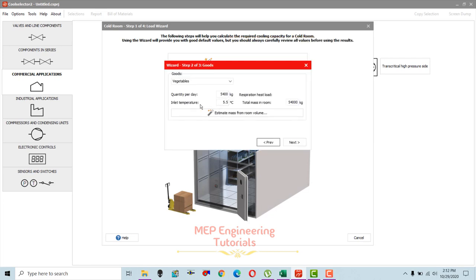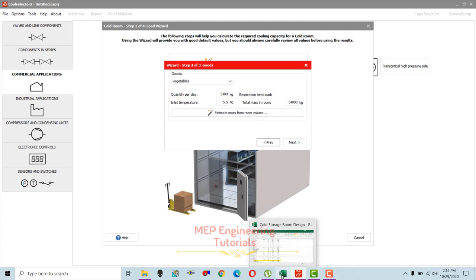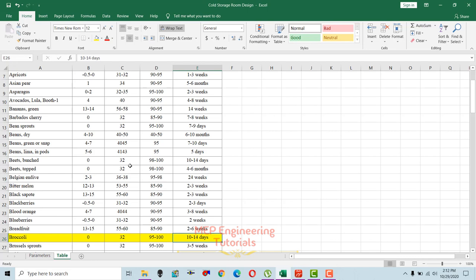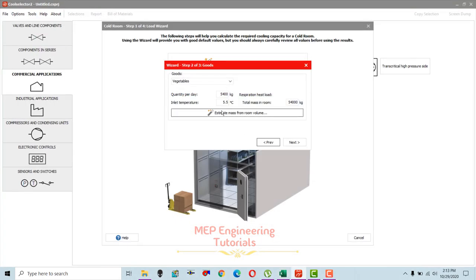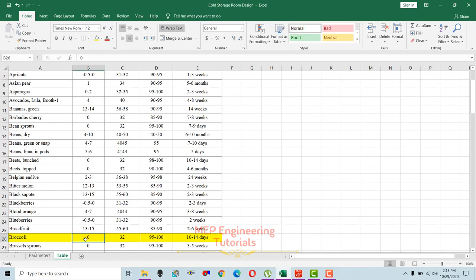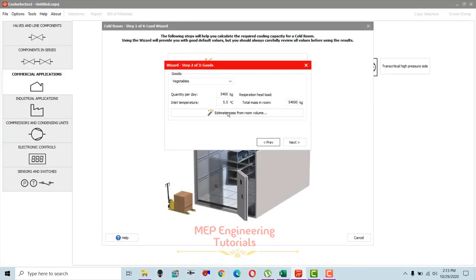One more thing to consider is inlet temperature. By default it's 5.5 degrees Celsius. The inlet temperature should be 5 degrees above the storage temperature, because goods are assumed to be pre-cooled before storing in the cold storage room. Since cold room storage temperature for broccoli is 0 degrees Celsius, 5 degrees above that means we keep inlet temperature at 5 degrees Celsius. Then select next.